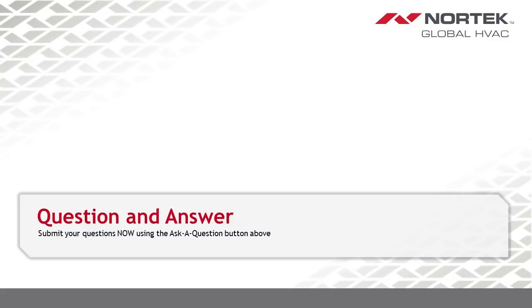Question here, Jeremiah: total static pressure on these furnaces - what were they tested at, and what will they be offered at? They're tested to a max static rating of 0.5, which is what we offer today. And the cooling airflow charts will be rated up to 0.8.